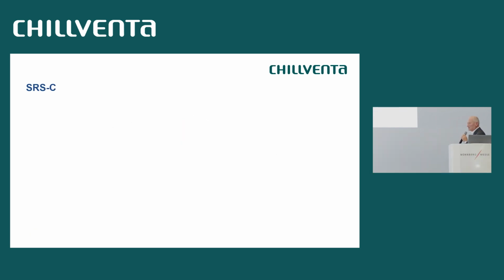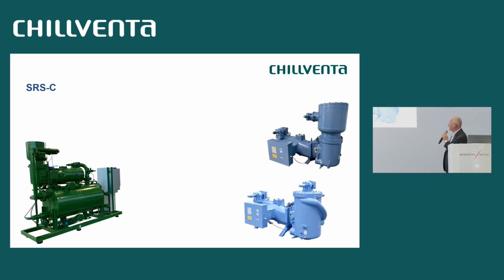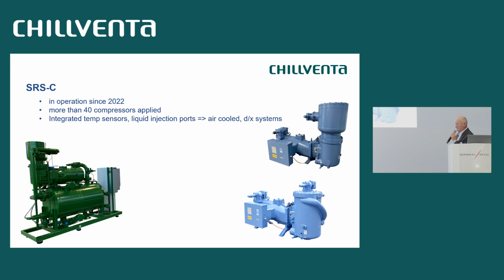Now I come to our newest baby, the SRSC, which is a compressor with the integrated oil separator. This compressor was introduced to the market with one model in the year 22. We have more than 40 compressors applied, mainly in Denmark and in Germany. It comes with integrated temperature sensors and liquid injection ports, so that we can also now do air-cooled and dry expansion systems and have these liquid injection ports as emergency cooling systems for the very hot day and the high condensing pressure.